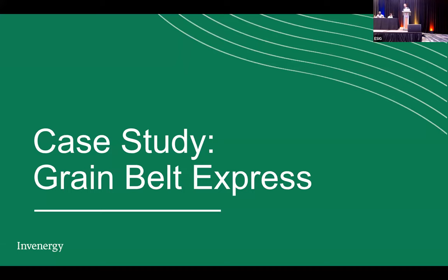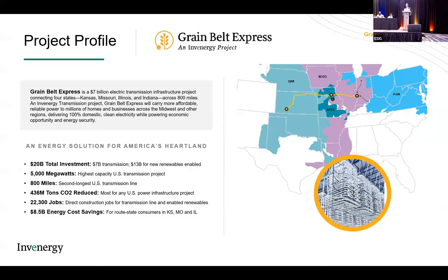And so now we'll dive into one of Invenergy's projects, the Grain Belt Express. Just at a high level, this is what the project looks like. It starts in southwestern Kansas, goes through about 540 miles to Missouri with an HVDC line, and then another 260-ish miles to Illinois, where it connects to PJM. So all in all, it's about 800 miles of HVDC line, and it does have that three-terminal nature. The total rating will be 5 gigawatts, 600 kV HVDC bipole with dedicated metallic return.